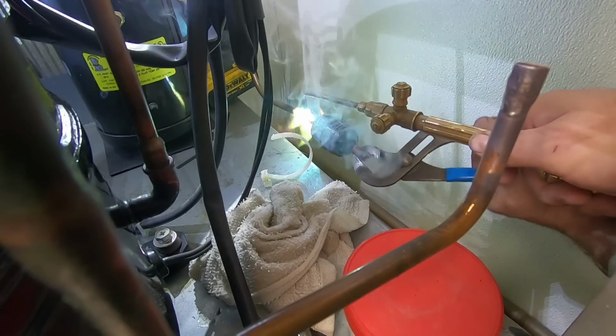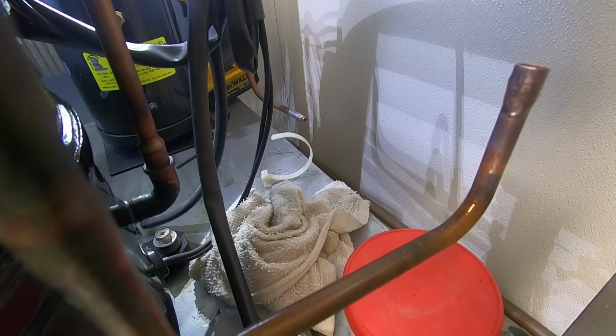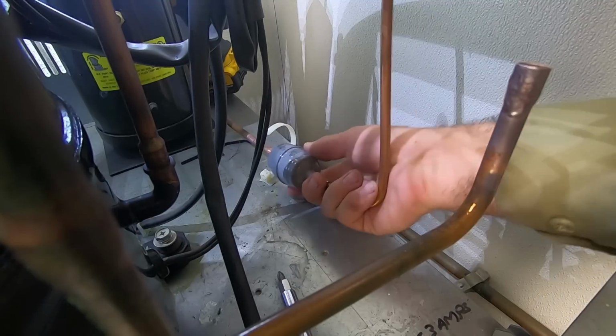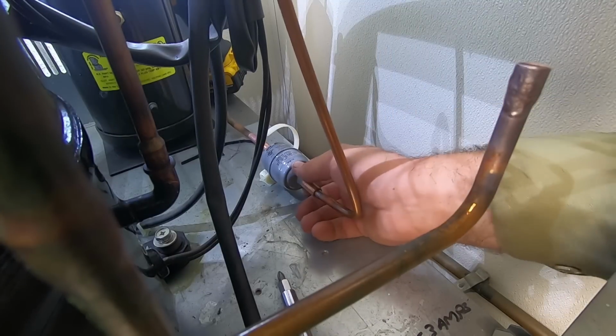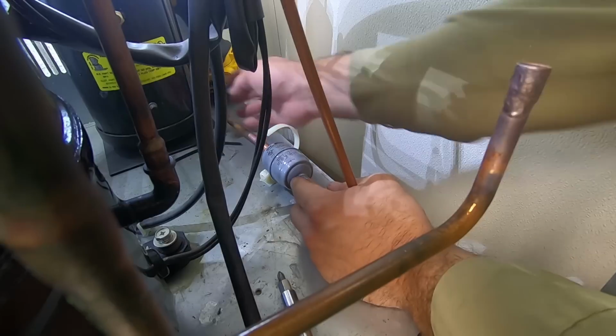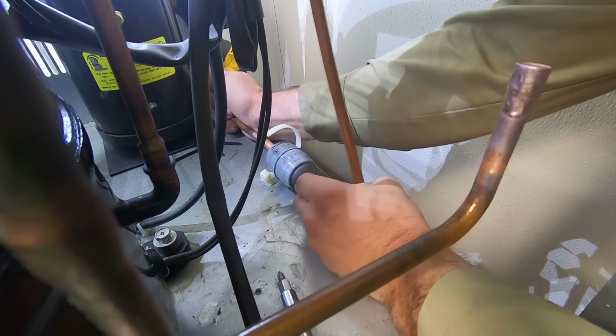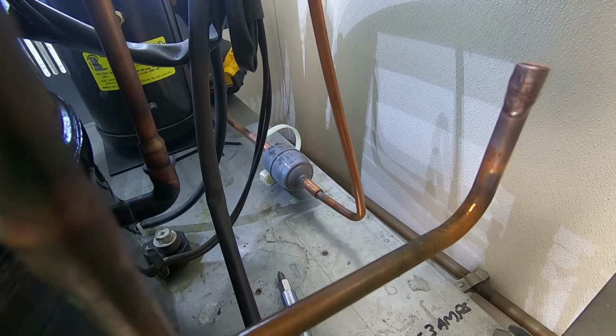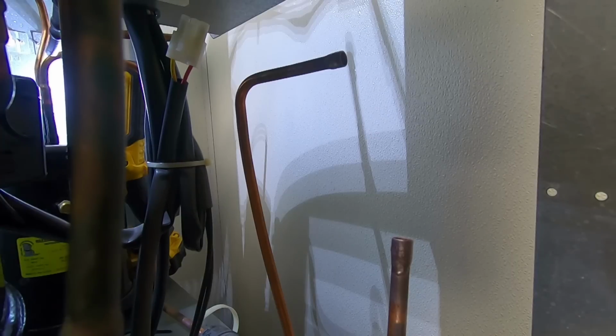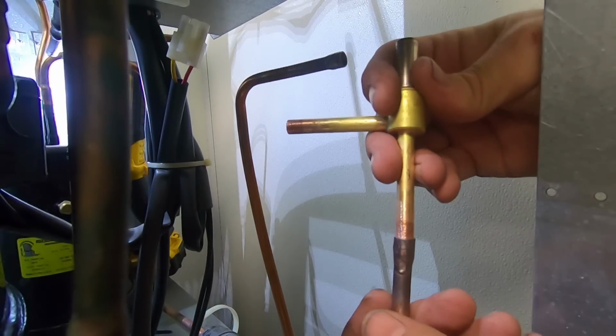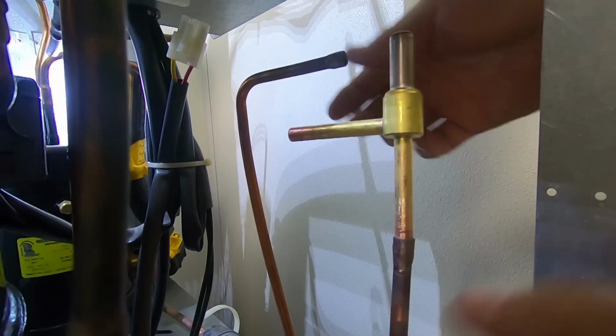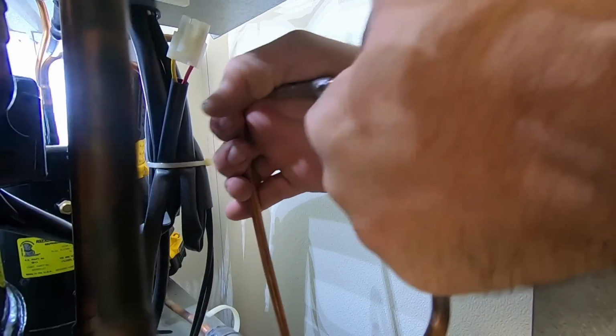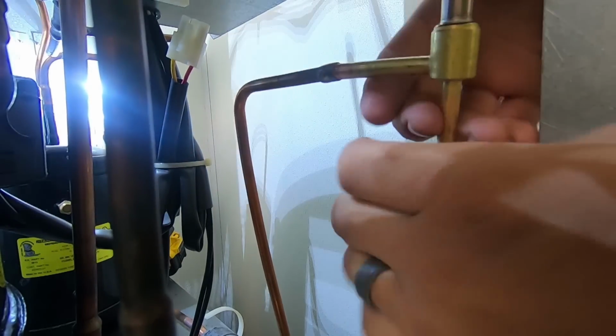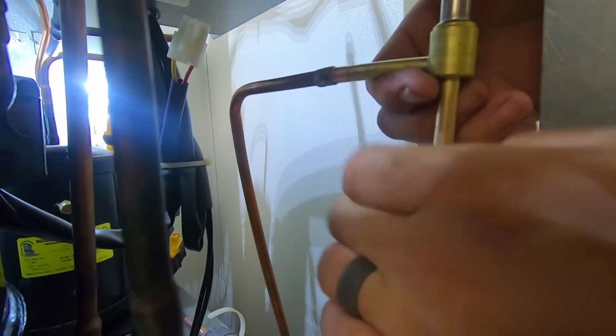Look at that inlet to the dryer and you'll notice a puff of smoke coming out right at the tail end. That's because this entire time while I'm fitting, unbrazing, and brazing everything in, I've got nitrogen purging through the system to help. Now, I'm not a perfect technician, I'm not always brazing with nitrogen, but in certain situations when I can, I do, and it definitely helps so that I can pull a better vacuum and make sure we don't get any contaminants we don't need in the system.